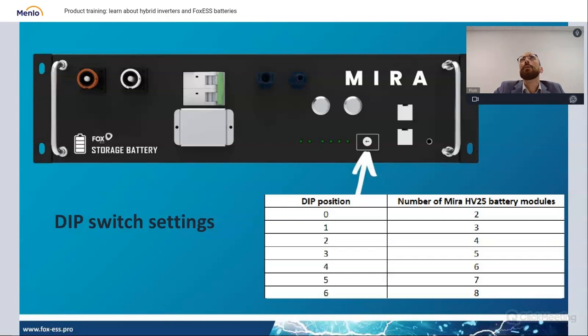This arrow on the dip switch tells the BMS how many modules we connected. The minimal amount on which the BMS operates is 2 batteries for H1 systems. So this is the default position of this dip switch. 0 on the dip switch means that we connected 2 batteries. If we connect 3 batteries, we select 1 on this switch. And what if we have 6 batteries? Let's check. It's 4.